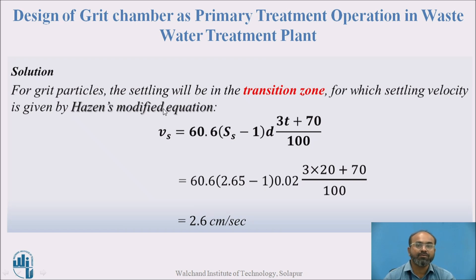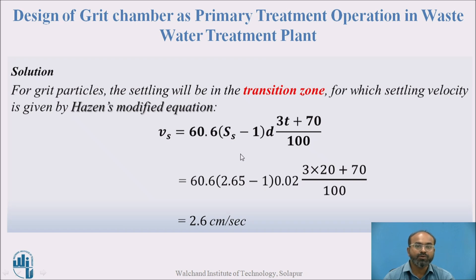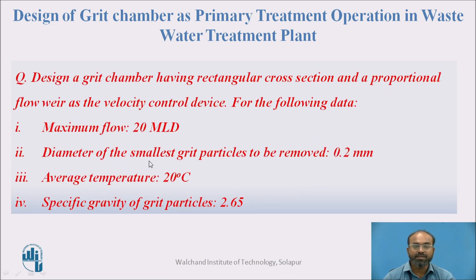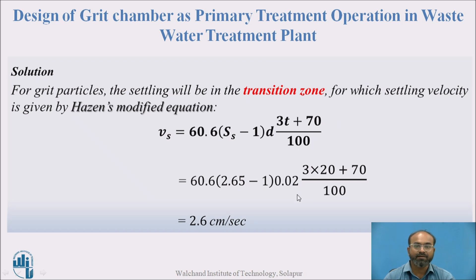First, I calculate the settling velocity of grit particles using Hazen's modified equation, assuming settling in the transition zone. Using the formula Vs = 60.6 × (Ss − 1) × d × (3T + 70) / 100, I put in values: specific gravity 2.65 minus 1, diameter 0.02 cm (converting 0.2 mm to centimetres by dividing by 10), temperature 20°C. This gives a settling velocity of approximately 2.6 cm/s.